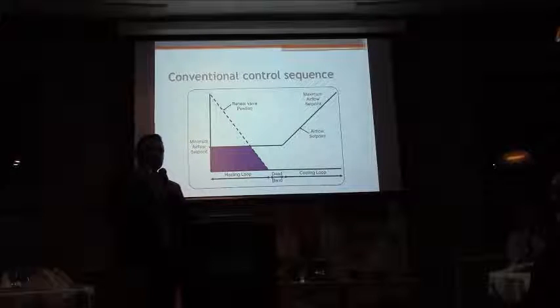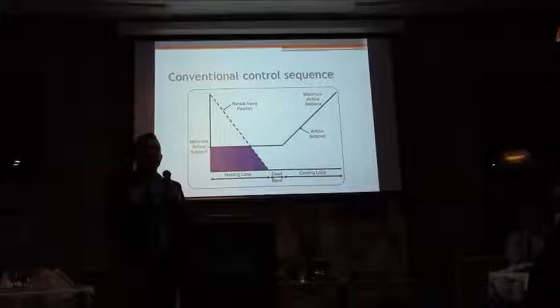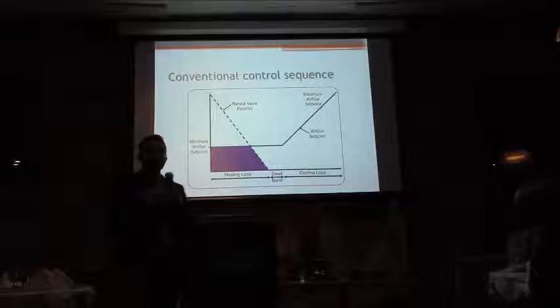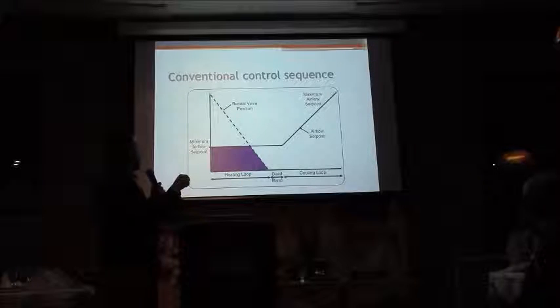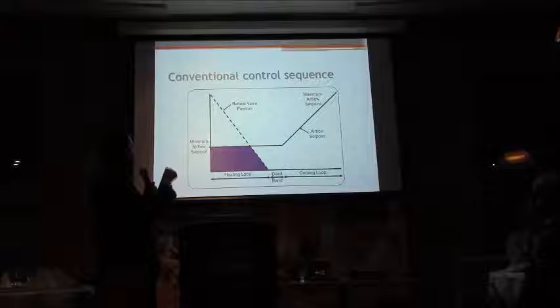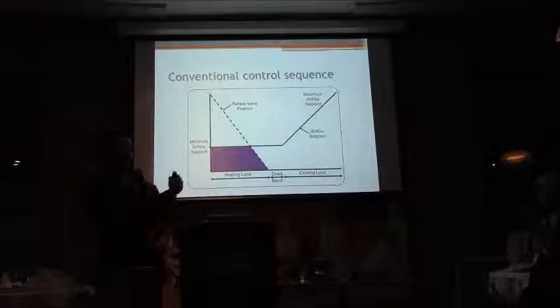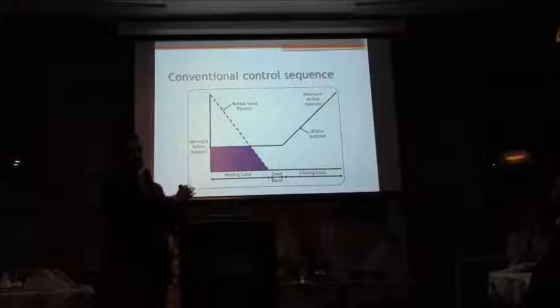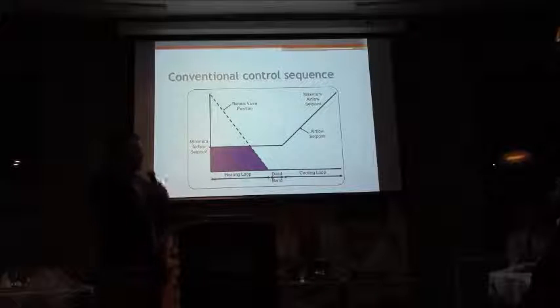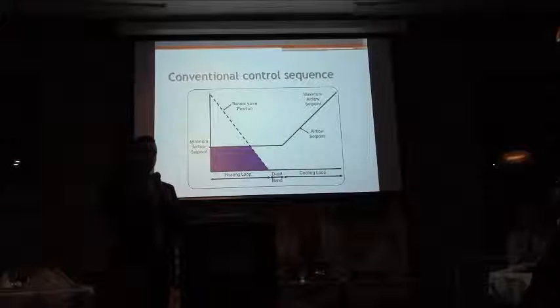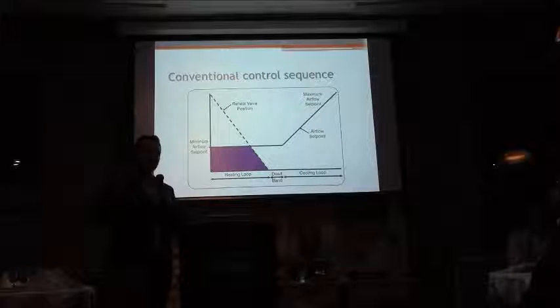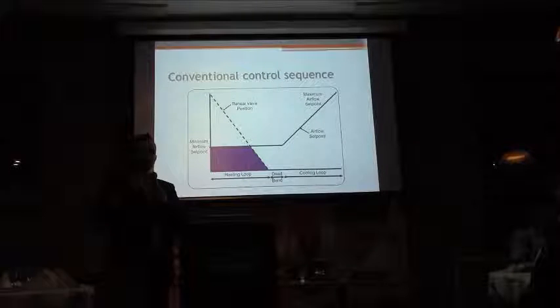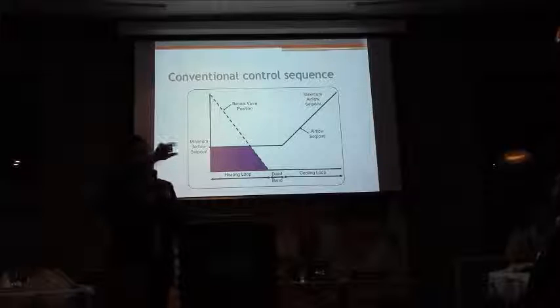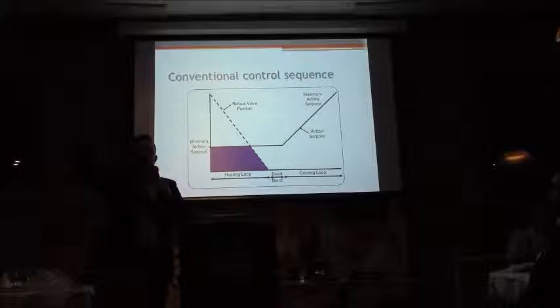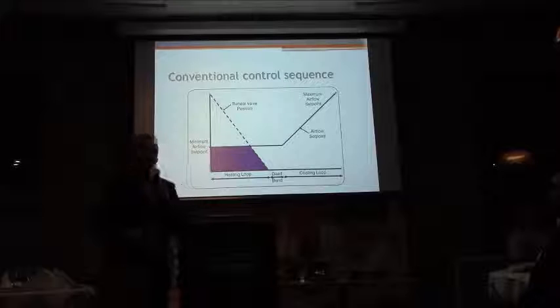And if you're going to heat through a diffuser, let's say like the cone diffuser, the air typically comes out at lower velocities than high induction. And if you add to that the fact that you're operating and heating at minimum airflow set point, and that's the typical control sequence that we see in Canada, then first of all, you don't have a lot of CFMs. You're operating at minimum CFM, you're distributing hot air through a diffuser that has low velocities. Your hot air is just going to stagnate there. It's just going to stay in the ceiling. It's never going to come down into the occupied zone.